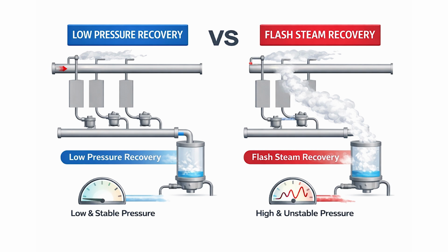There is another condition: factories where the back pressure after the trap is not stable. This relates to the condensate recovery system. If only condensate is collected, back pressure is usually low and stable. But when flash steam is also collected, back pressure increases. More importantly, it becomes unstable. When differential pressure changes, the discharge capacity of an orifice changes significantly. In other words, when back pressure is high and unstable, an orifice trap becomes difficult to apply.